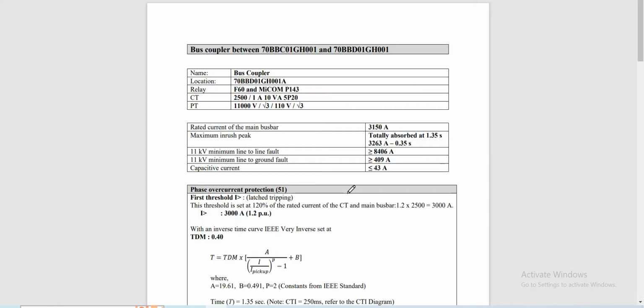This is the bus coupler between 70 BBC bus and 70 BBD bus. So the relays being used are the F60 from GE and the MiCOM P143 from Schneider Electric. Our CT ratio is 2500:1 ampere, burden is 10 VA, and class 5P20. Our PT ratio is 11,000 to 110 volts. Our 11 kV minimum line-to-line fault is rated 8,406 ampere. 11 kV minimum line-to-ground fault is 409 ampere.